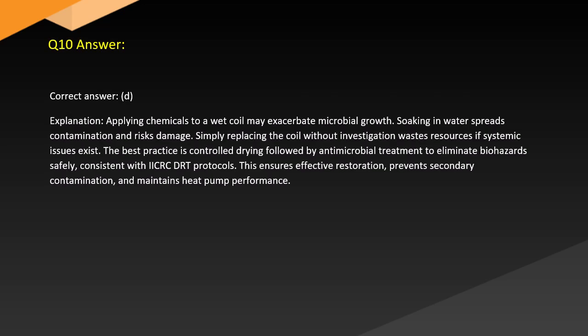Answer. Correct answer: D. Explanation. Applying chemicals to a wet coil may exacerbate microbial growth. Soaking in water spreads contamination and risks damage. Simply replacing the coil without investigation wastes resources if systemic issues exist. The best practice is controlled drying followed by antimicrobial treatment to eliminate biohazards safely, consistent with IICRC DRT protocols. This ensures effective restoration, prevents secondary contamination, and maintains heat pump performance.